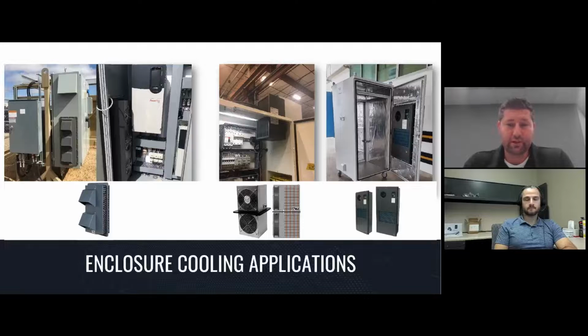The final one on the right is our vapor compression cooler—essentially an air conditioner, but designed narrow enough to mount on a door, as shown here in an electronics cabinet. That's often preferred because door space is usually available and not occupied by electronics or insulation. We have many door mount applications with a fairly straightforward cutout and minimal intrusion into the cabinet. Our vapor compression coolers range from about 1 kilowatt to 5 kilowatts of heat rejection at a 0-degree temperature gradient.